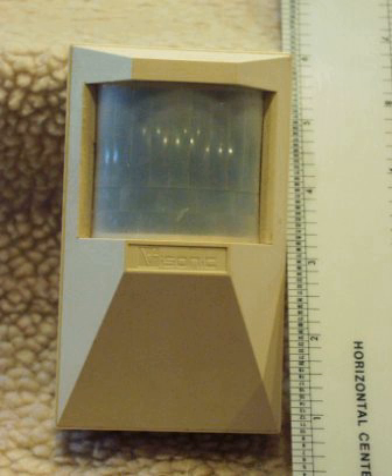Some larger PIRs are made with single-segment mirrors and can sense changes in infrared energy over 30 meters (100 feet) from the PIR. There are also PIRs designed with reversible orientation mirrors which allow either broad coverage 110 degrees wide or very narrow curtain coverage, or with individually selectable segments to shape the coverage.